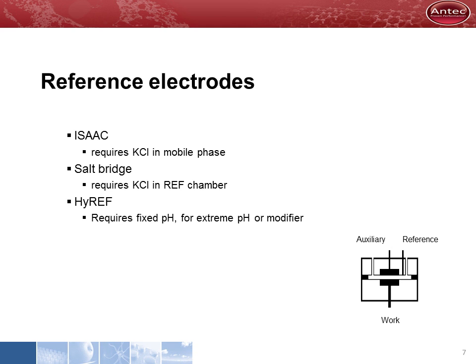Reference electrodes are only functional when they have an equilibrium with certain ions in the solvent surrounding them. For stable operating conditions, these ions must be present at a fixed concentration. The ISAAC and the salt bridge are silver-silver chloride electrodes that require chloride ions in solution. The HyREF is a hydrogen reference electrode which requires a fixed pH of the solvent.